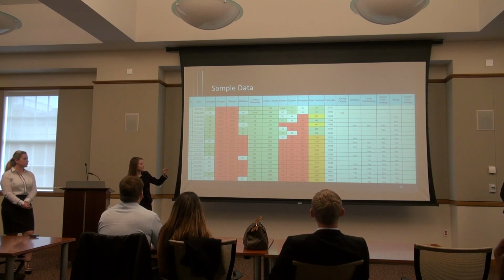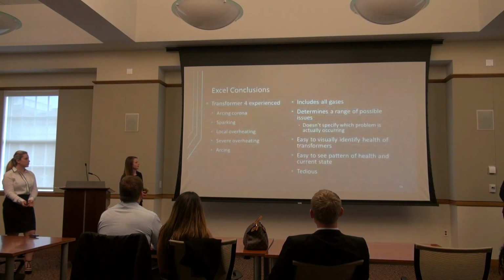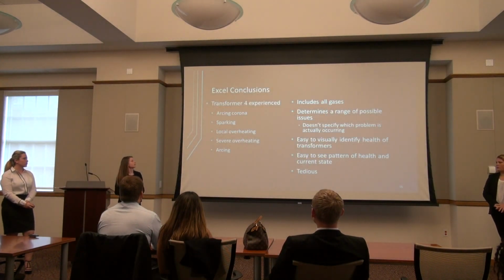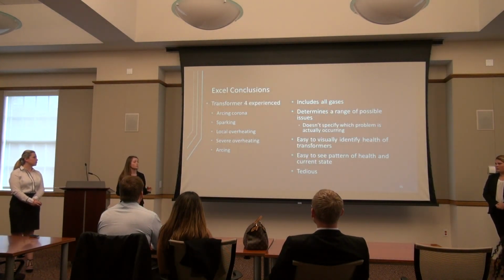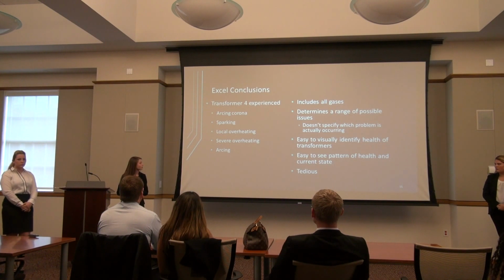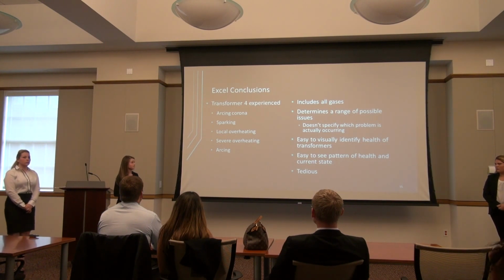As you can see, as the transformer gets older, more of these problems could be occurring within it. So the conclusion from this analysis is that transformer 4 is probably experiencing, at these points in time, a combination of arcing corona, sparking, local overheating, severe overheating, and arcing.